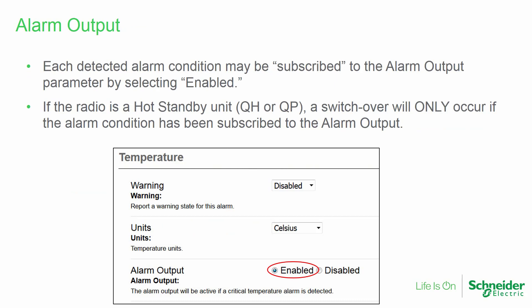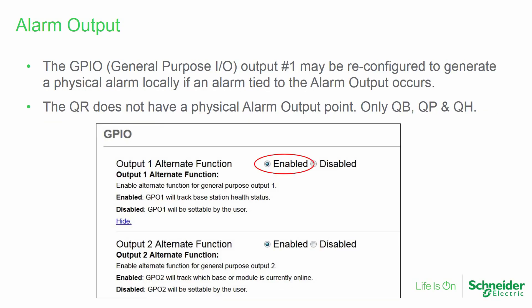Each detected alarm condition may be subscribed to the alarm output parameter by selecting the Enabled button on the alarm's setup page. If the radio is a hot standby unit, a QH or QP, a switchover will only occur if the alarm condition has been subscribed to the alarm output. The General Purpose IO or GPIO digital output point number 1 may be reconfigured to generate a physical alarm locally if any alarm tied to the alarm output occurs. Note that the QR does not have a physical alarm output point — only the rack-mounted QB, QP, and QH, which each have four digital outputs, have this feature.